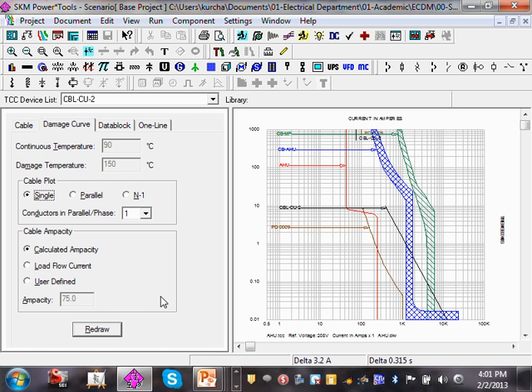Okay, so let's make it even more interesting. Let's look at the 1,000 amps here. Go all the way to the line. How long can this conductor handle 1,000 amps? All these are short circuit conditions, abnormal. Take this, here's 1,000, go all the way up until you hit right here, okay? Everybody's okay with that? If you cross-reference it here, it's between 1 and 2, say 1.5 seconds. So that conductor that carries 75 amps can actually carry 1,000 amps for 1.5 seconds.